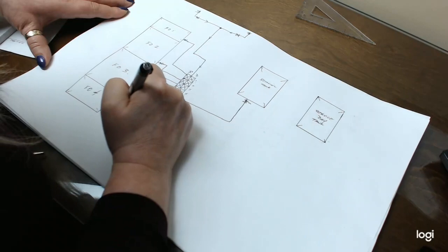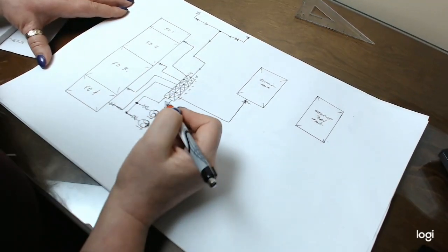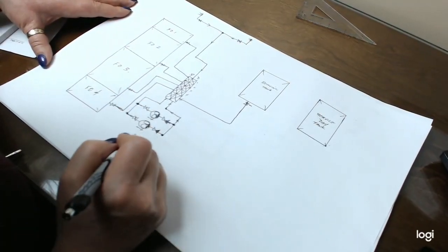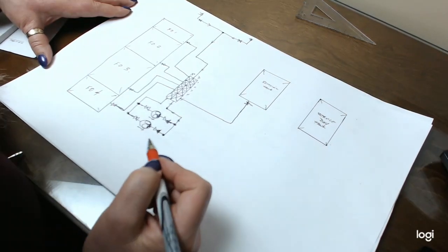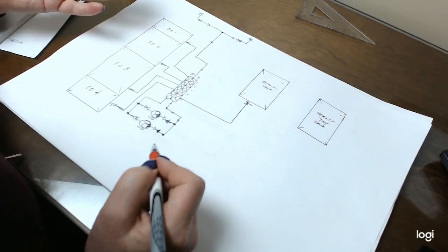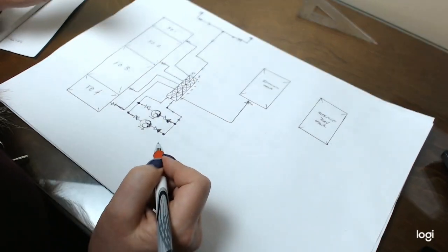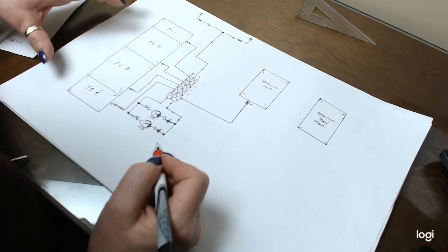Now, when you are looking at the direction of these pipes, they are designed to do both suction and discharge. So you have to calculate them and usually take the bigger of the two. When you look at the calculations, you'll see one flow velocity for suction and one flow velocity for discharge. Calculate them both and then put the size in.